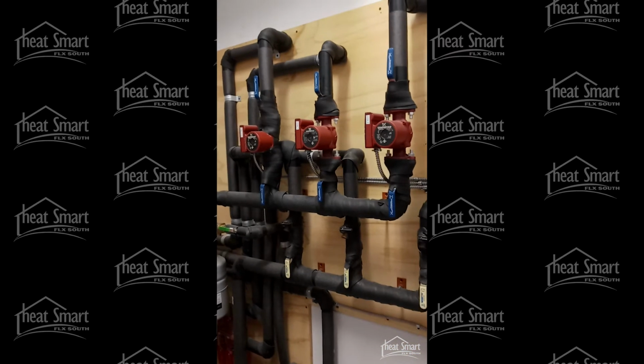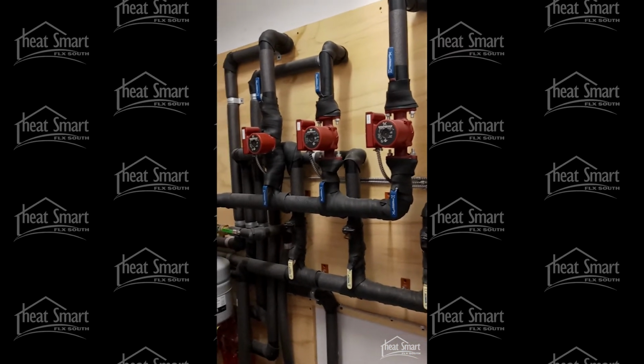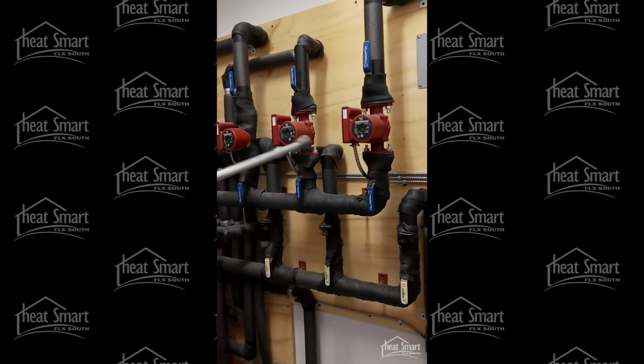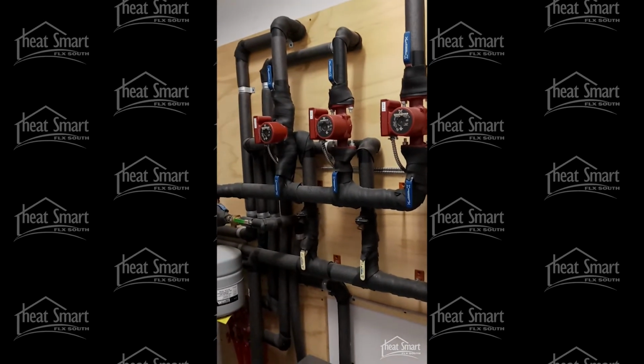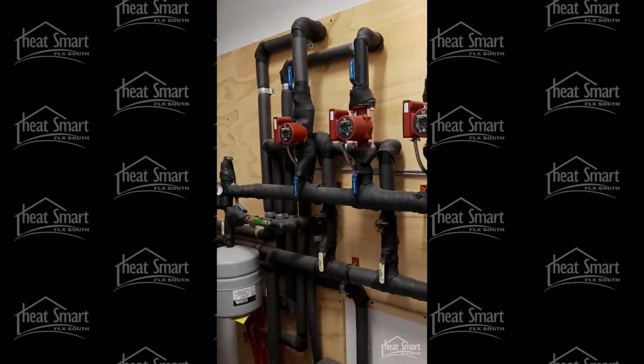And what are these red items here? There are three of them in a row. Those are circulator pumps. Basically, there are three zones in the building. Zones 1 and 2 are hot water radiant heat, so there are two thermostats in the building. And then this is the fan coil, which is the air conditioning.